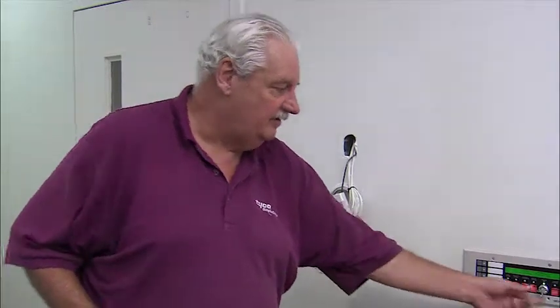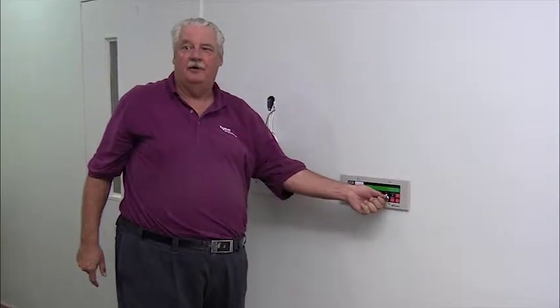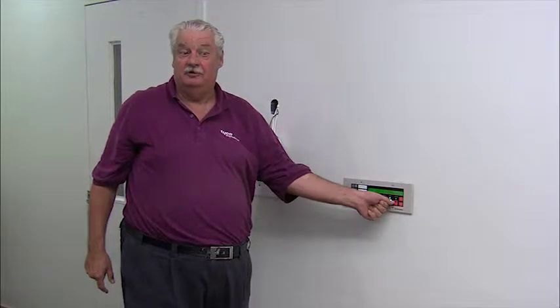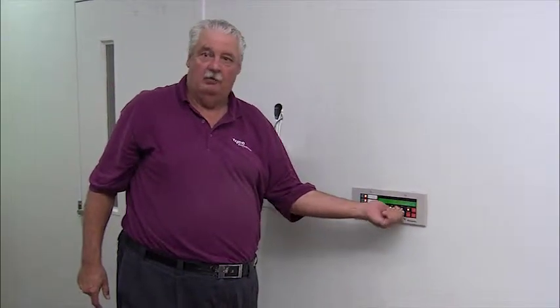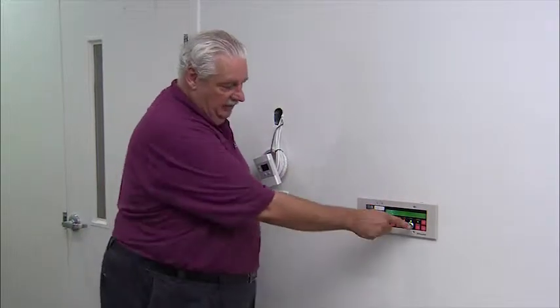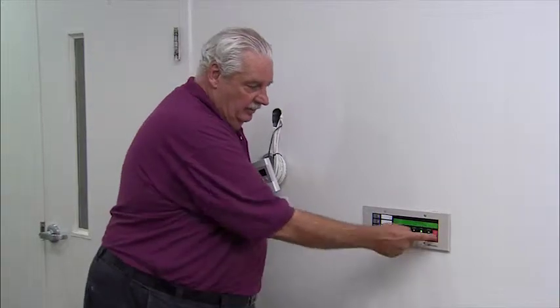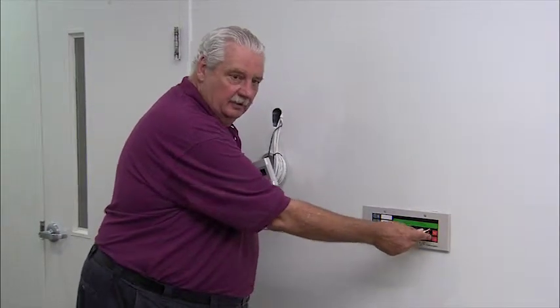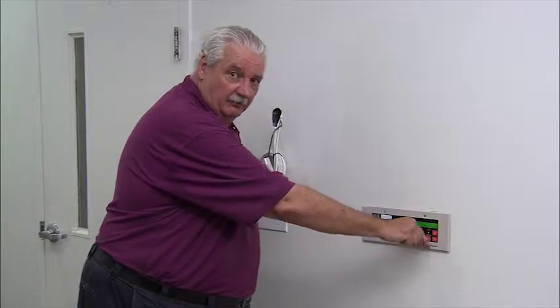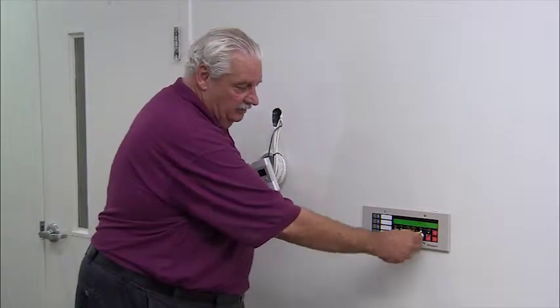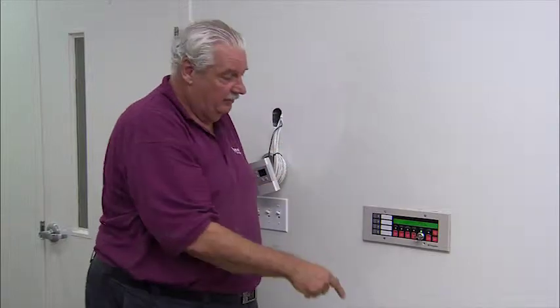In order to activate any of these keys, you need to turn it up to enable. The reason the fire department doesn't want the key in there is because somebody's going to leave it turned and leave these buttons active. They don't want these buttons active. So the key needs either to be out, maybe hanging under there someplace, or turned in the up position. Otherwise the silence and reset buttons aren't active, okay? You need to turn the key. It's going to display the same thing as the main panel, and then you can press your buttons and do the same thing, acknowledge conditions.